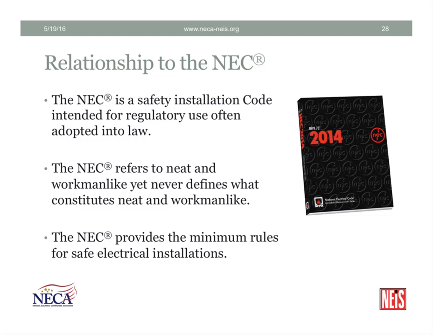The NEC is the minimum. That means it contains the rules that are the least amount that one must do to result in a safe installation. The NEC is typically adopted into law at the state level by jurisdictions and even down at the city and local levels. It's typically a legal document once it's adopted into law.